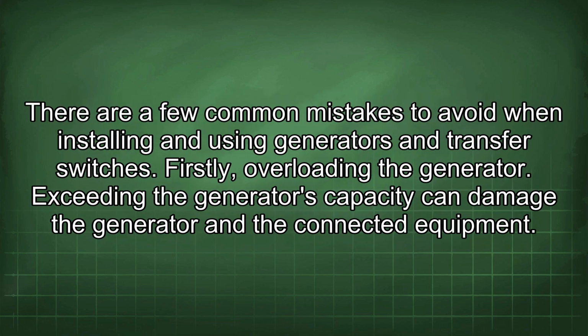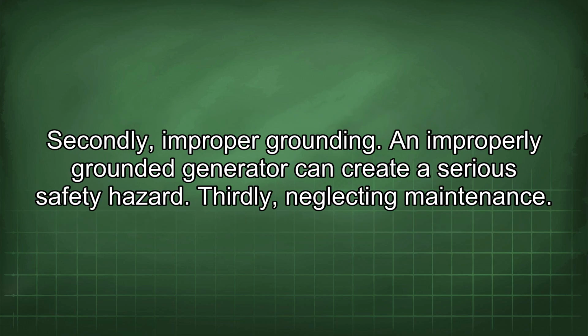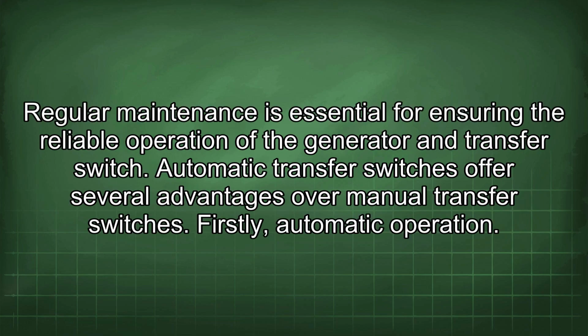There are a few common mistakes to avoid when installing and using generators and transfer switches. Firstly, overloading the generator. Exceeding the generator's capacity can damage the generator and the connected equipment. Secondly, improper grounding. An improperly grounded generator can create a serious safety hazard. Thirdly, neglecting maintenance. Regular maintenance is essential for ensuring the reliable operation of the generator and transfer switch.